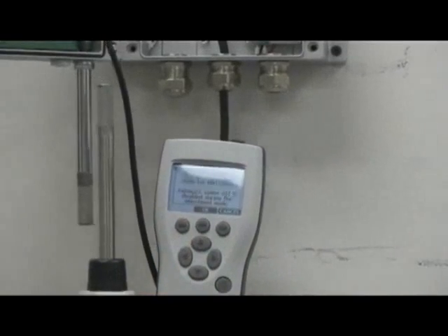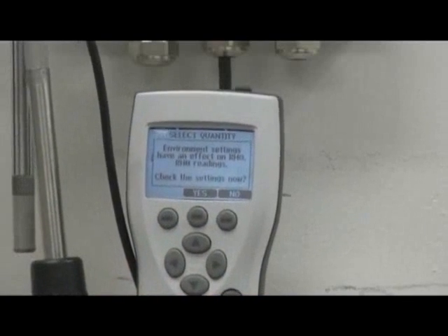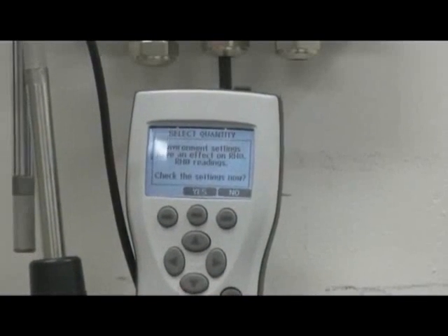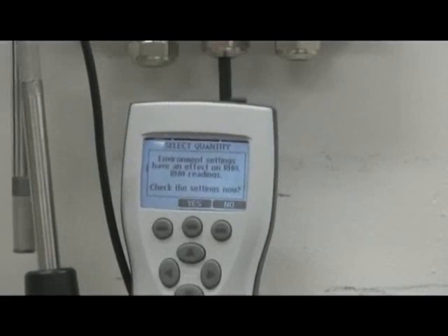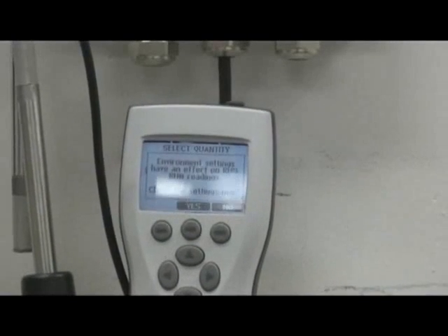Step 4. Press OK and select RH. Now you'll see the message: environmental settings have an effect on RH, check settings now. This is simply verifying that the sensors are both at atmospheric pressure and not at different pressures. So we select no.